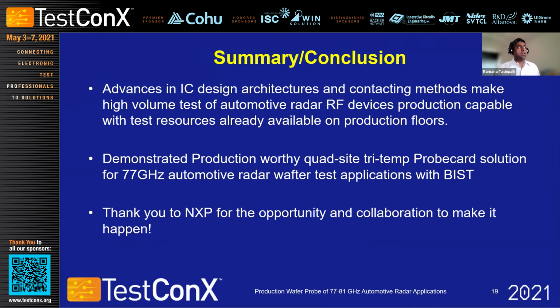Okay. Did you do the calibration before an RF test? What kind of calibration do you do before an RF test? Yes, we do. We actually have the ability in-house to measure the S parameters of each individual high-speed RF line in the probe head. So if you heard Aaron Long's presentation from yesterday, he described that we provide S parameters for each of the high-speed RF paths along with the probe head or probe card product. We can measure just through the probe head or into the PCB, through the entire probe card and through the cabling. And then we'll provide that as a calibration methodology.